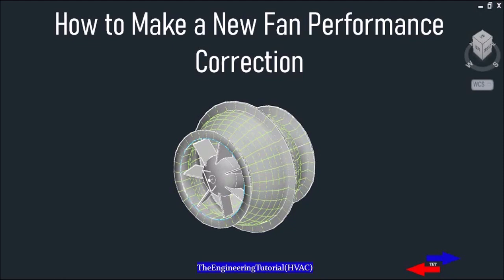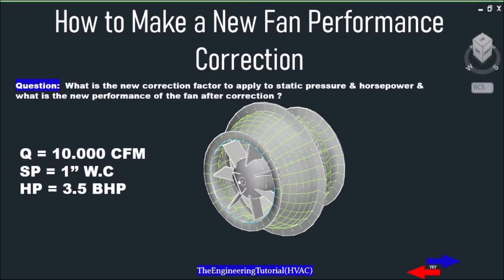70 degrees Fahrenheit at sea level. When operating conditions of fans vary significantly from standard conditions, air density should be taken into consideration. Fan pressure and horsepower vary directly with air density; however, fan air volume is not affected by air density.